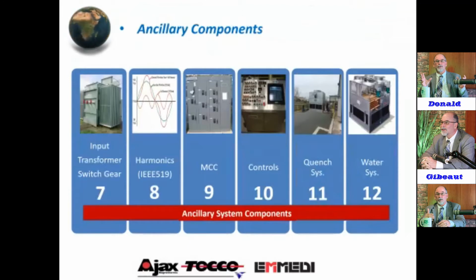So then we get into the ancillary supportive equipment of the line, which is what we covered: the input transformers and switchgear, harmonic filters. Here in the US, we have a specification, IEEE 519. All induction equipment outputs a harmonic. And typically we're focused on the 5th, 7th, 11th, and 13th harmonic. We do offer harmonic filters that can bolt onto the power supply, where we do a harmonic study, and we can filter out to this IEEE 519 coming out of our power source, which is your heaviest source of power typically in these facilities. All the rest of the equipment, any coating systems, anything else, is typically on another transformer. So you have dedicated transformers for the induction, but we definitely control harmonics, and we do that so that harmonics don't come back into the equipment.